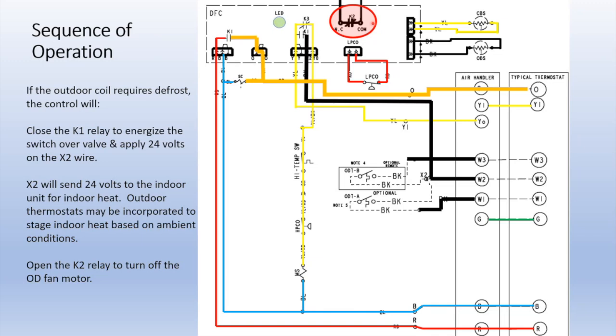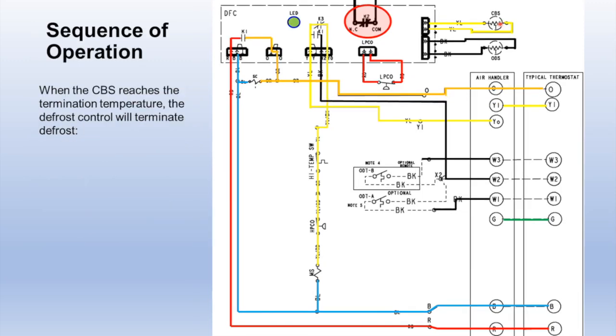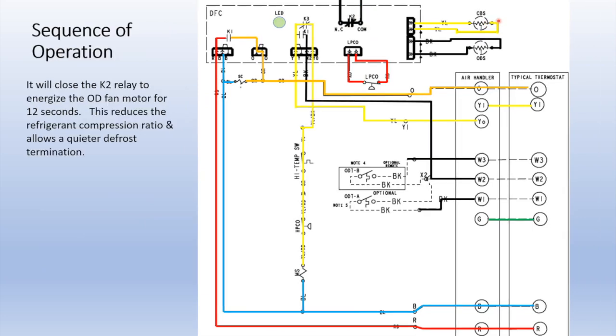So it's going to continue to defrost for a minimum of 1 minute, and then once that coil sensor reaches 47 Fahrenheit, it's going to terminate the defrost. And the first thing that's going to happen is it's going to turn the outdoor fan back on, because without the outdoor fan running and it essentially being in cooling mode, our head pressure is going to shoot up fairly high. So it turns that outdoor fan on to reduce head pressure.